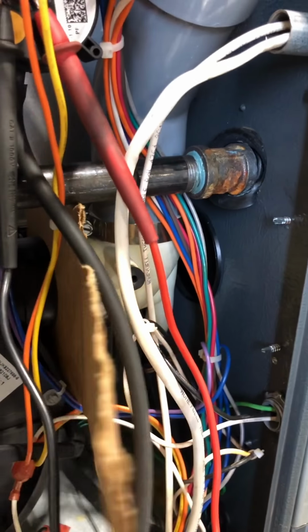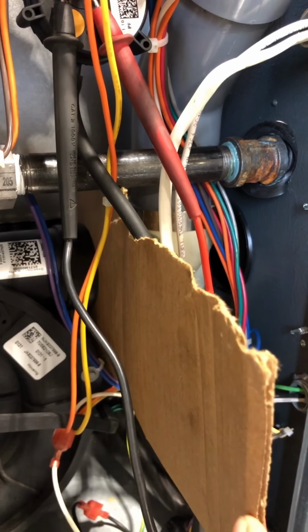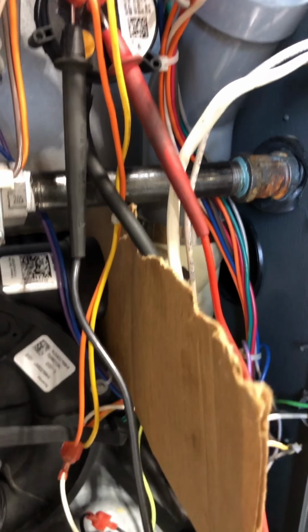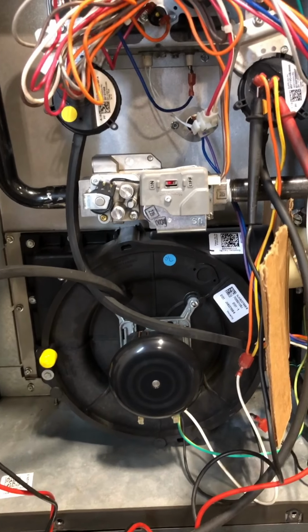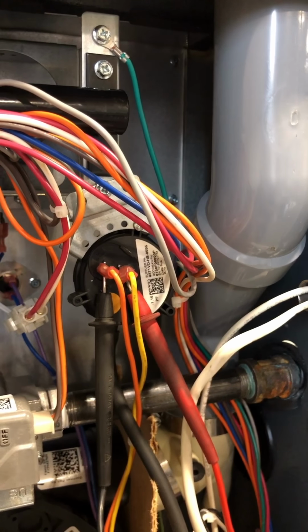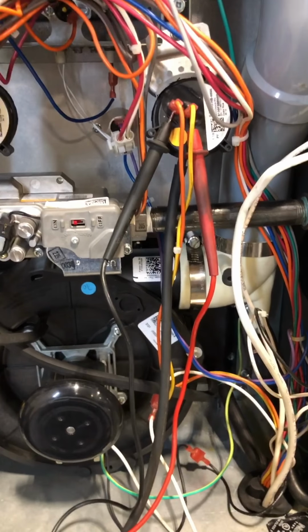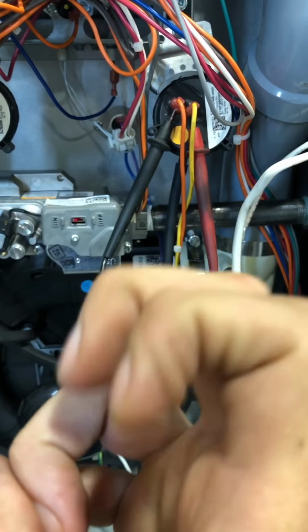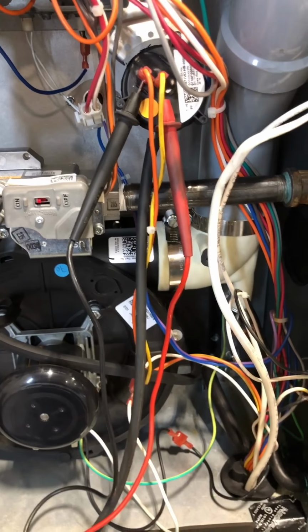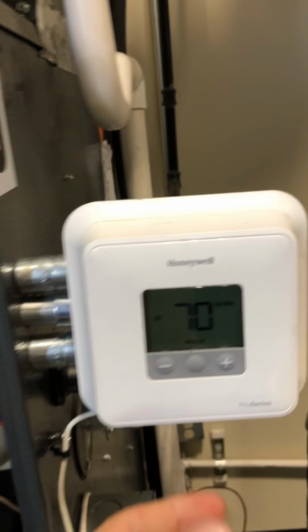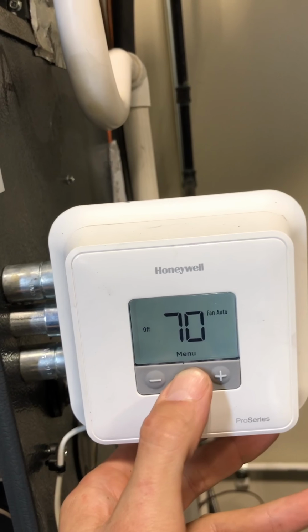But what I've done is I've blocked it. So the furnace will not continue in its process until we clear the blockage, until we can prove that this inducer motor is running by closing that switch. Okay, I've removed the blockage, my piece of cardboard, and we'll fire this thing back up and see what happens now. Call for heat.